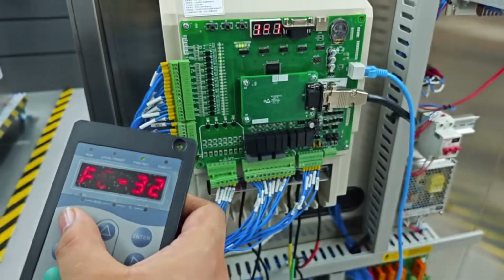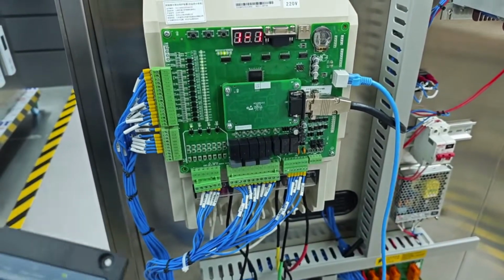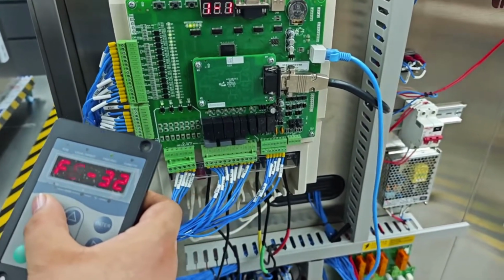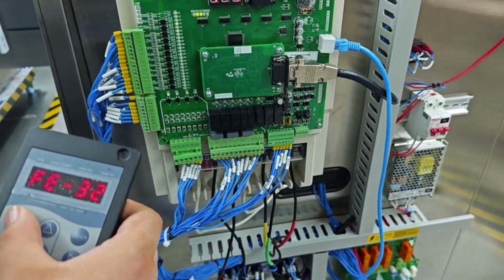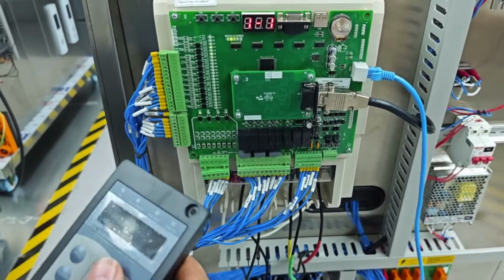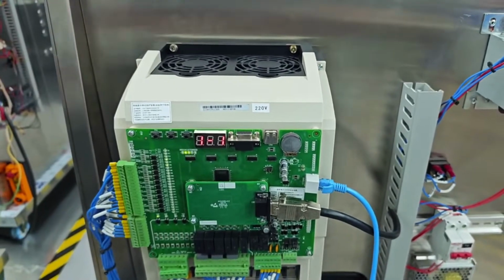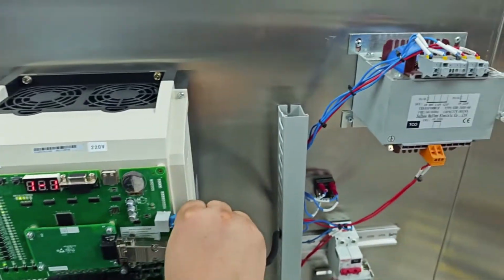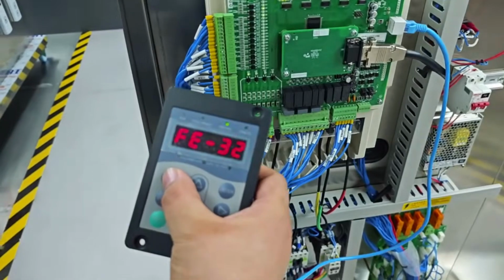然后还有一个 E37406故障。There is also an E37406 fault. 屏蔽参数在 FG-08 bit 0。We need to change FG-08 bit 0 equals 1 to mask the E37406 fault. 这个故障大部分需要调整我们的制动器。This fault normally needs us to adjust our brake.